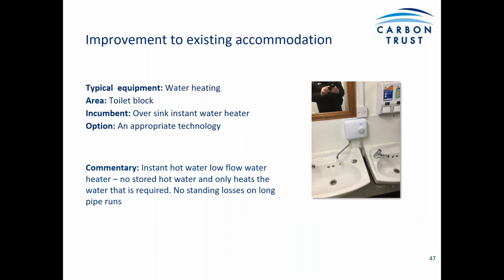And then just looking at the water heating, the typical kind of over sink electric heating. That's an appropriate technology, rarely used at the best of times anyway, but they're fairly cheap, fairly robust, and will only heat the water that is required. So you do away with the likes of the standing losses and such like on other systems.